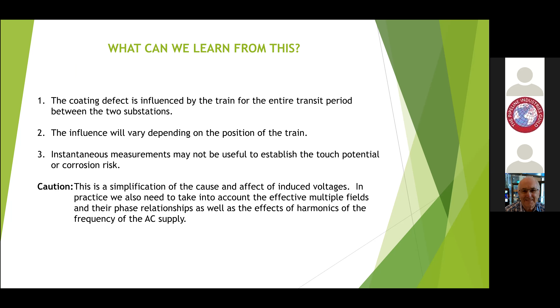Well, the first thing to bear in mind is that corrosion only takes place on the pipe where the bare steel is exposed to the electrolyte, whether that electrolyte happens to be concrete, water, soil. I haven't discussed in this presentation the corrosion risks that exist on steel reinforcement in concrete, in tunnels and crossings and so on, because this is just related to pipelines, but the same risks are there. So it's not too hard to understand that if you want to get rid of the AC corrosion risk, you need to get rid of the AC, because without the AC, you haven't got a problem. The reason that the AC is induced in your pipe and it leaves the pipe is because it wants to get back to where it came from. So if you can remove the AC, then you won't have an AC corrosion risk.